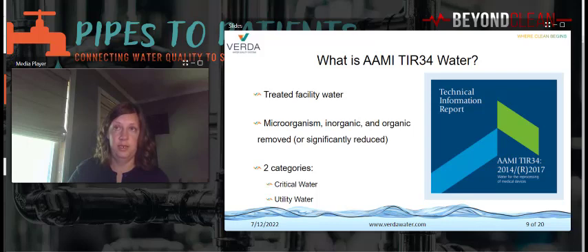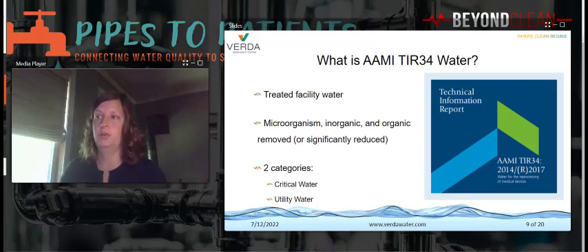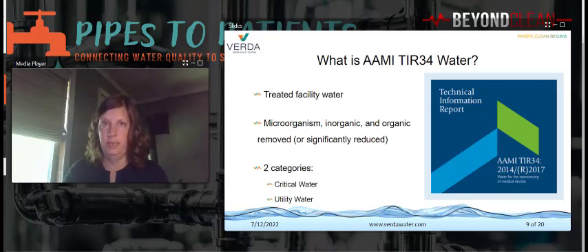Organic materials in sterile reprocessing can include bioorganic, dissolved, colloid, and aggregate organic matter. Some examples: soil or silt, clay, the decomposition of plant materials such as algae. Usually you're measuring total organic carbon in your water to check for the organic carbon. AAMI TIR 34 defines two categories of water quality, critical and utility. They use 13 different water quality parameters to define the critical and utility water, although 6 are given preferential focus.